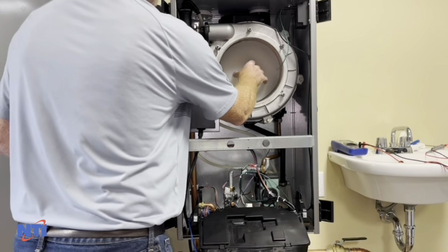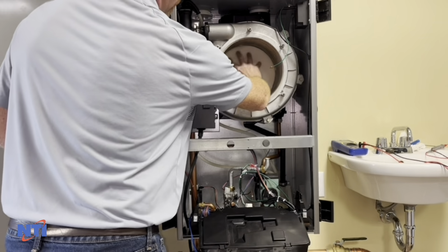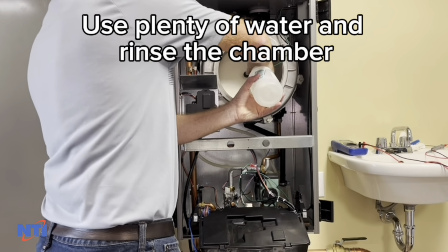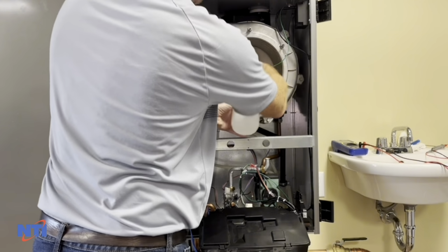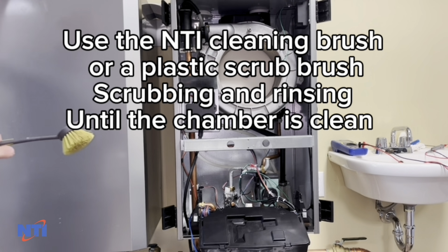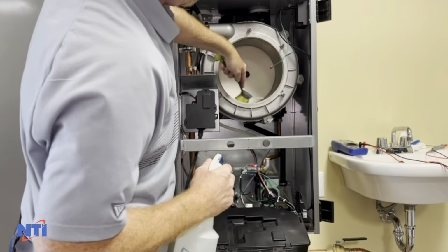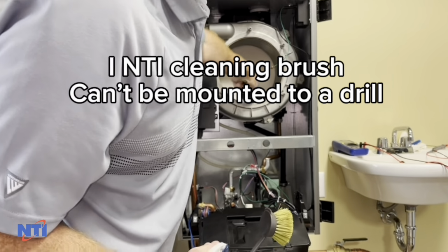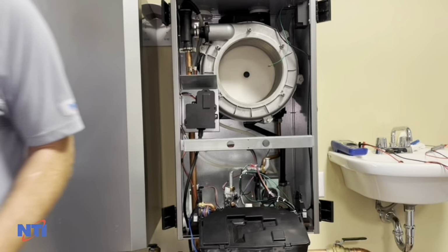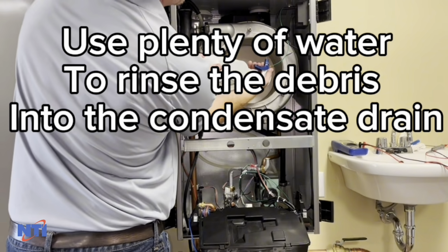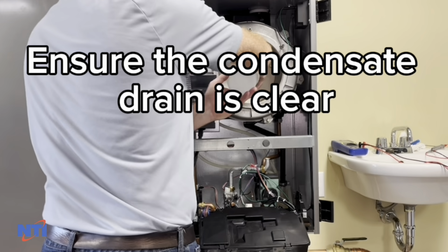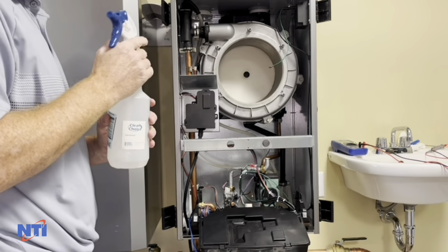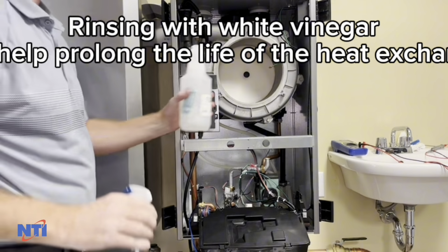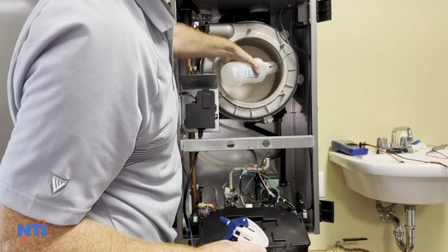Using large amounts of water, spray down the inside of the boiler and scrub it with a scrub brush such as this or the NTI cleaning brush until it is thoroughly clean. Use large amounts of water to rinse any loose debris down into the condensate drain. Ensure that you clean out the condensate drain before leaving the job site. Spraying down the interior of the boiler with white vinegar will help prolong the life of the heat exchanger. Make sure to rinse the vinegar out before proceeding.